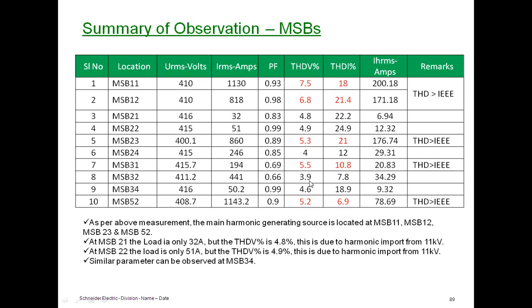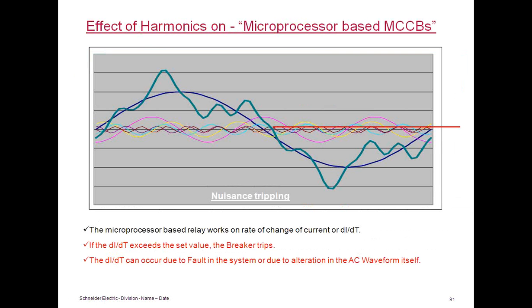Yeah. The main issues in this plant are twofold. One is the tripping of circuit breakers. They have microprocessor-based circuit breakers feeding welding loads. There are a lot of spot welding loads in the production line. So at some point of time, the circuit breaker trips. One tripping is causing about 2 hours of production outage.